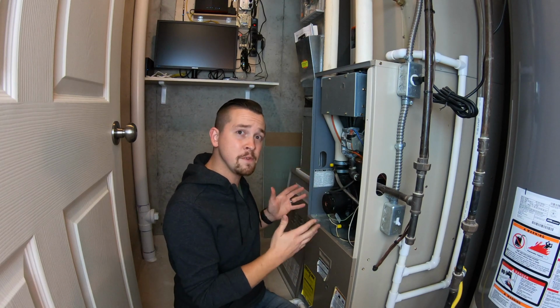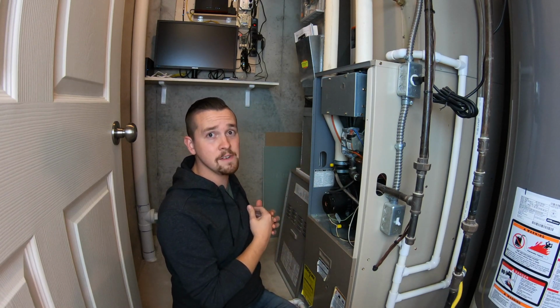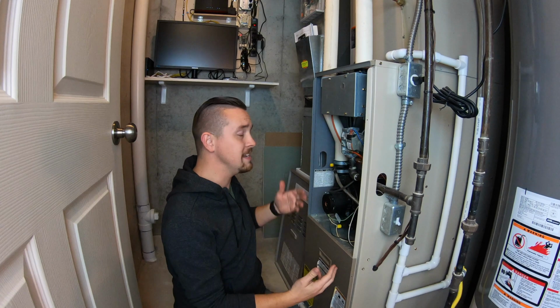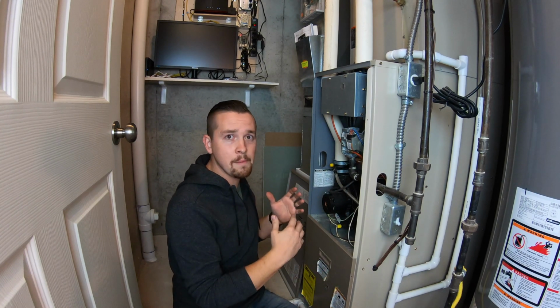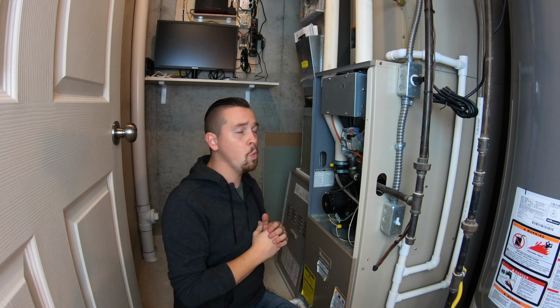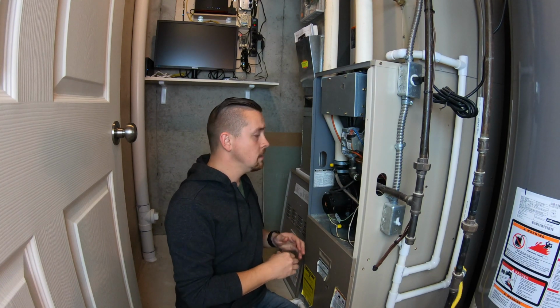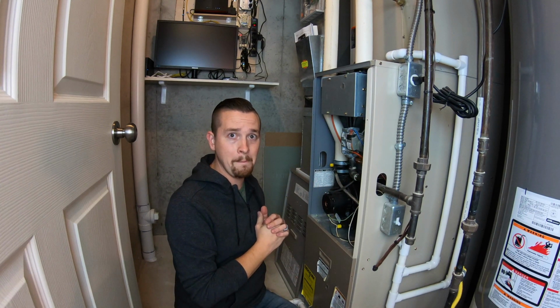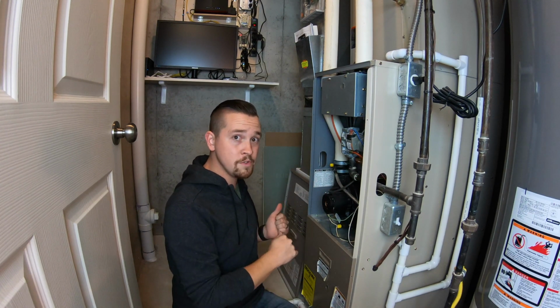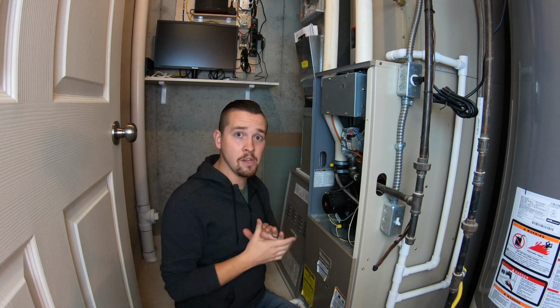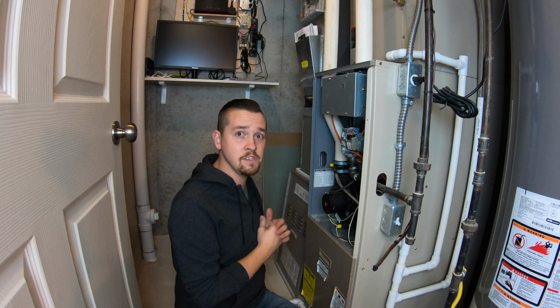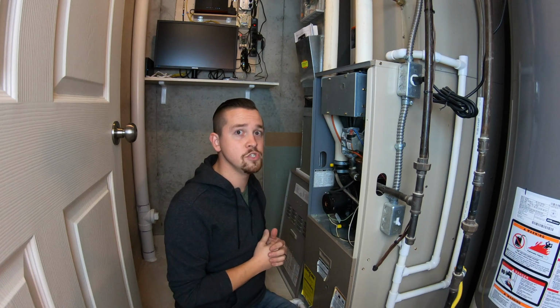Your furnace might be different than mine. It might not be a 90% efficient. It might be a 98 or it might be an 80. The general sequence of operations on a furnace that's 20 years old or less is going to be similar to mine here. If yours is older than that, then I would recommend calling a technician because there's other things that you need to be concerned about that a technician should check out.